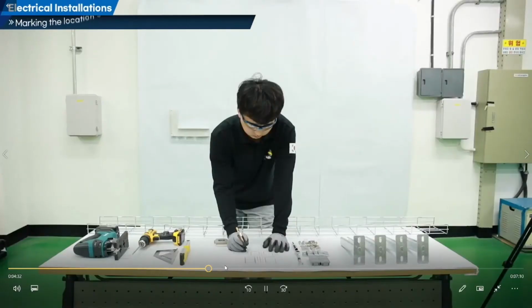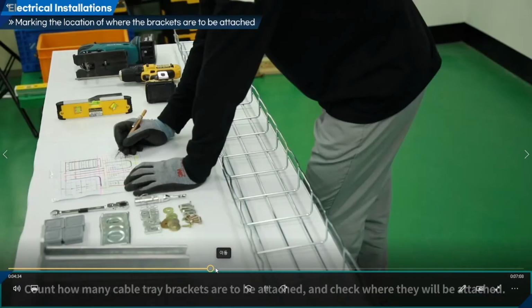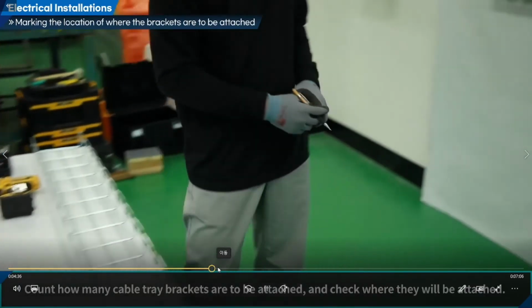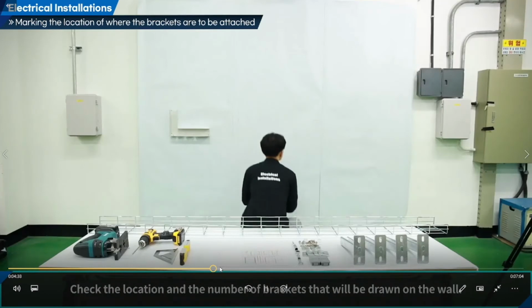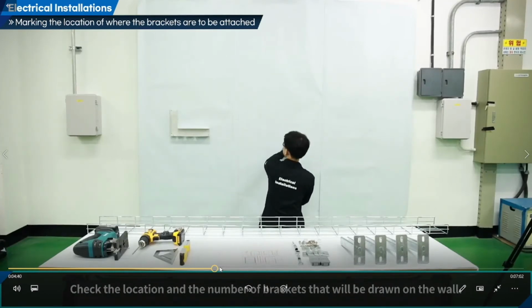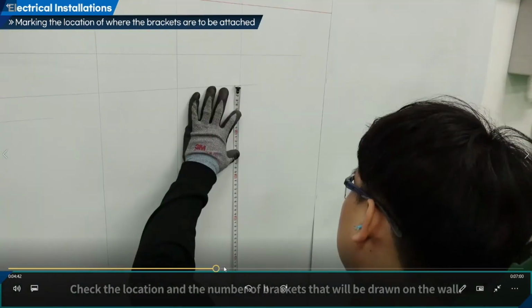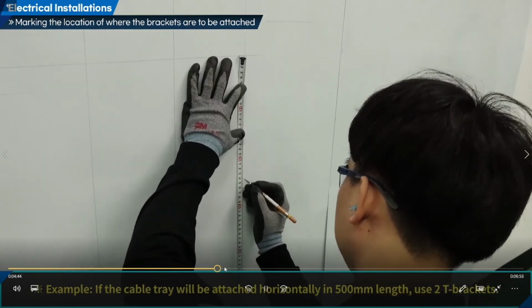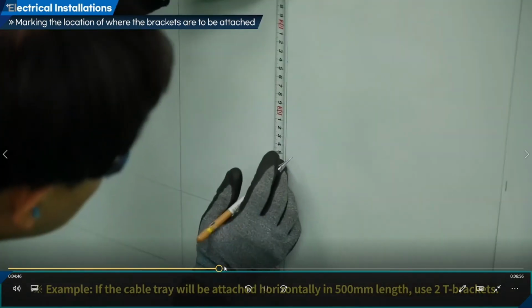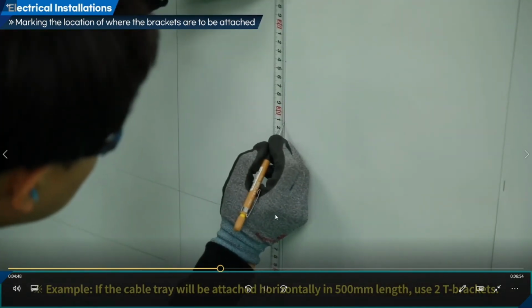We will mark the locations of where the brackets are to be attached. Count how many cable tray brackets are to be attached and check where they will be attached, marking the location and number of brackets to be drawn on the wall. For example, if the cable tray will be attached horizontally at 500 millimeter length, use 2T brackets.